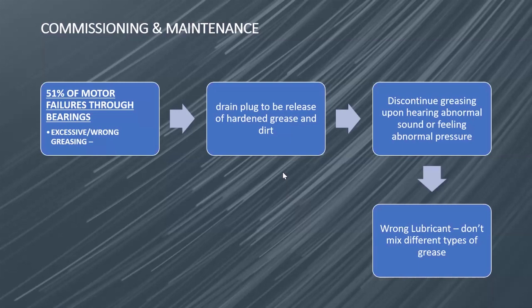So we must ensure during motor maintenance that the drain plug of the motor bearings is clean and clear, devoid of any blockages, so that when new grease is pumped into the bearing, the spent grease will have a clear path to move out of the motor, for the motor to be equipped with new grease for another running hours designed for it. And also when greasing, you have to be very cautious, because if you over-pressurize the bearings, chances are that the bearing lip seals will give way, and when they give way, you lose your motor because the grease will not be contained. So technicians are to be cautious when greasing motors and observe the pressure. When they observe any resistance, they have to stop.